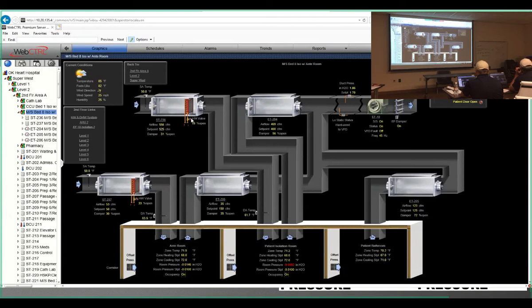It says, talking about room pressure, 2 minimum outdoor air exchanges per hour, minimum total is 6 for typical location. Okay, so I can calculate the volume of the room and typical room, and we can make sure that doesn't happen. We'll verify that. I would assume the outside air, room air exchange is figured at the air handler, obviously not at the room itself. Or it's like a 30% minimum. Right, so we give you 2 of the 6. Yes. It's a question I can ask.